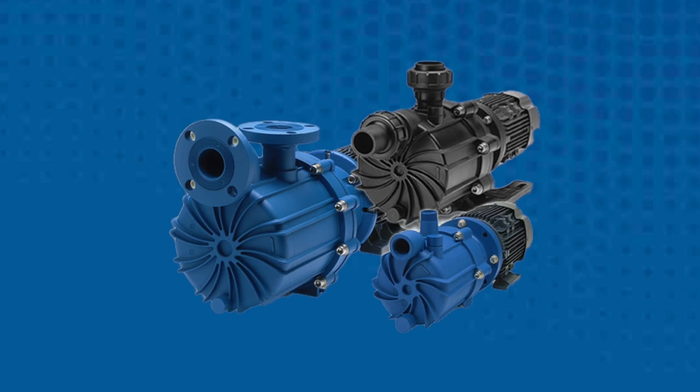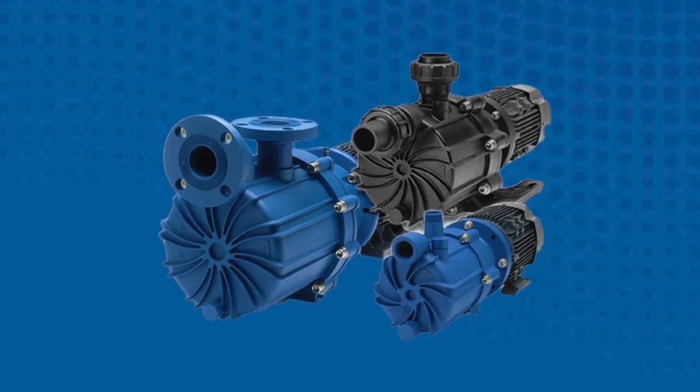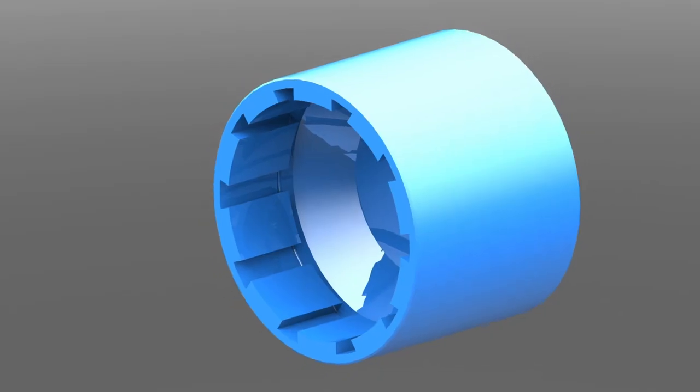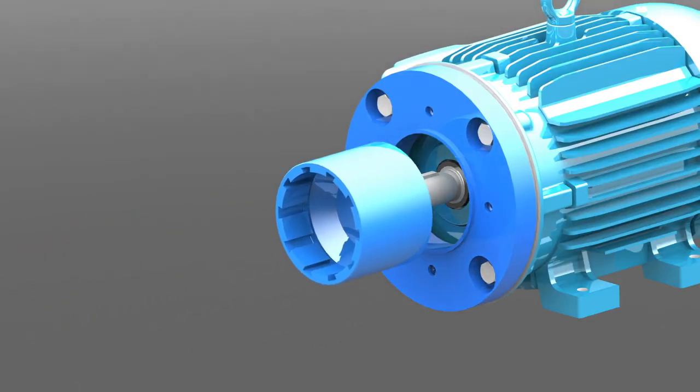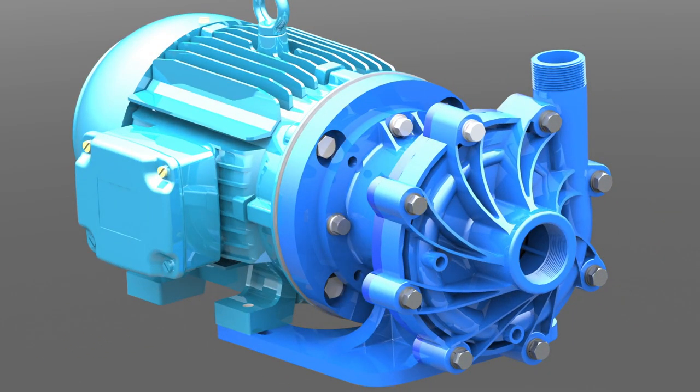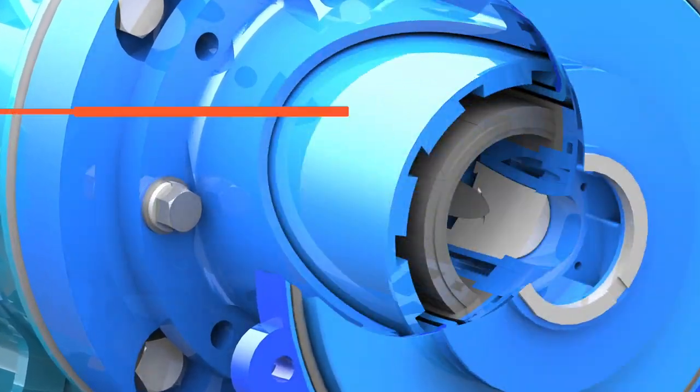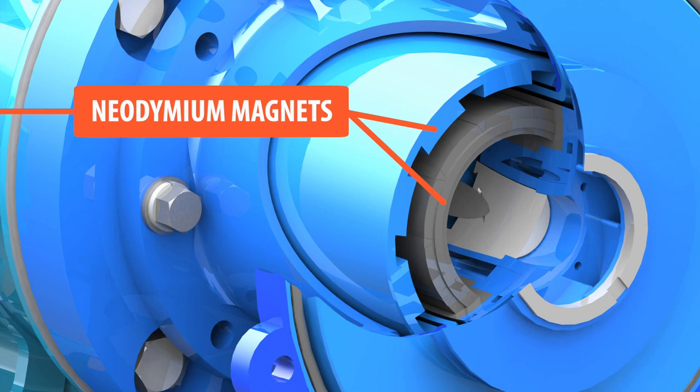Instead, Finnish-Thompson DB and SP series seal-less centrifugal pumps use a state-of-the-art magnetic drive. Our engineers designed a pump with powerful neodymium magnets mounted to the motor shaft. These rare earth magnets transfer the motor's force through a plastic barrier to magnets inside the pump that rotate the impeller.